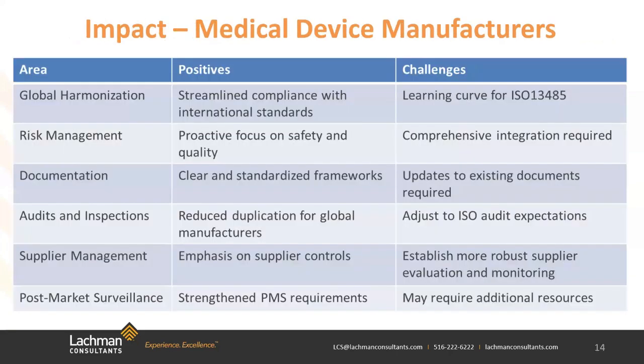Moving on. All right. So what's the impact to medical device manufacturers? On this slide, we show, at a high level, positives and challenges with the implementation of the quality management system regulation, which, as stated throughout the webinar, aligns FDA's requirements with ISO 13485. This may significantly impact some medical device manufacturers, especially those that have not implemented ISO 13485 or don't have an ISO certification.